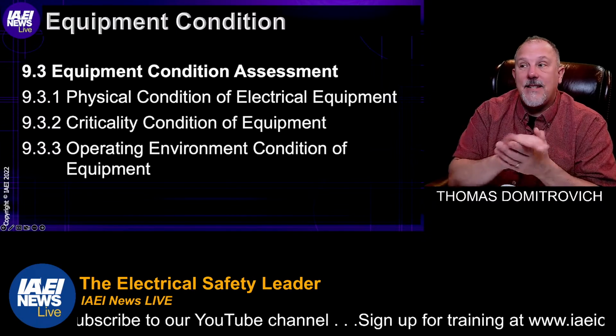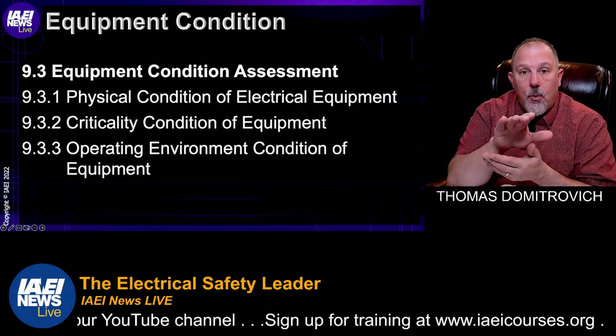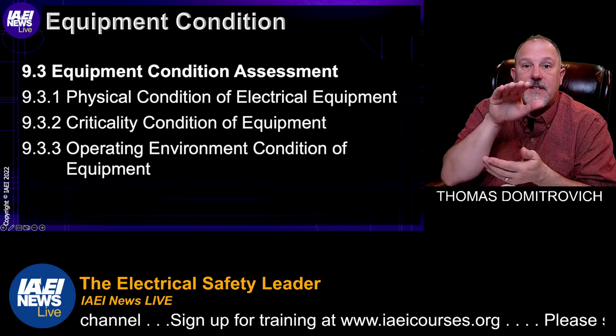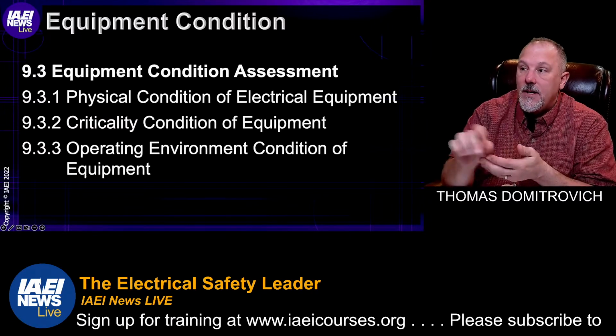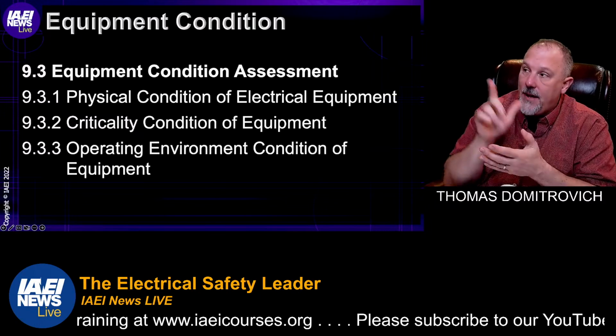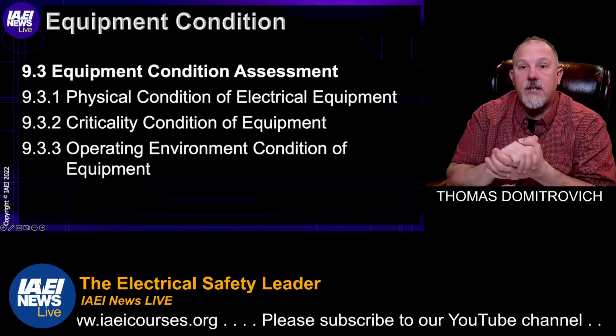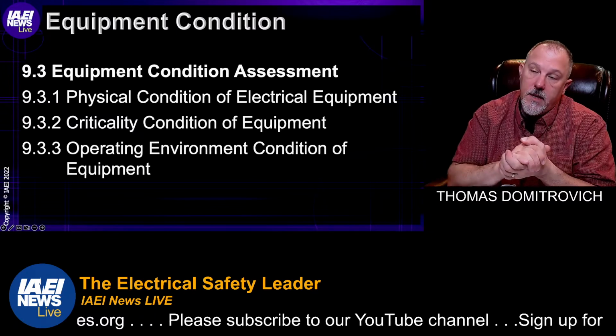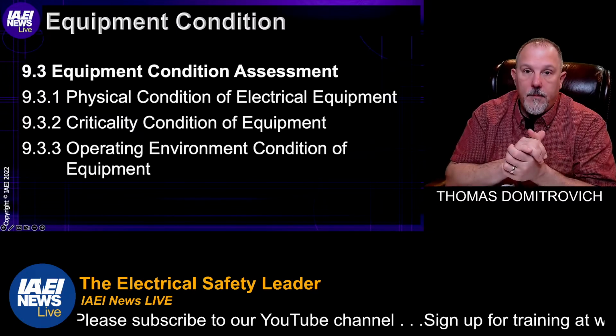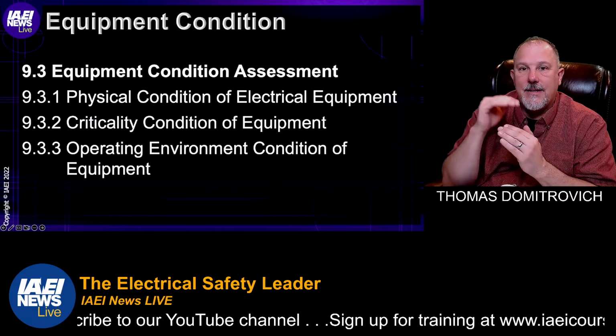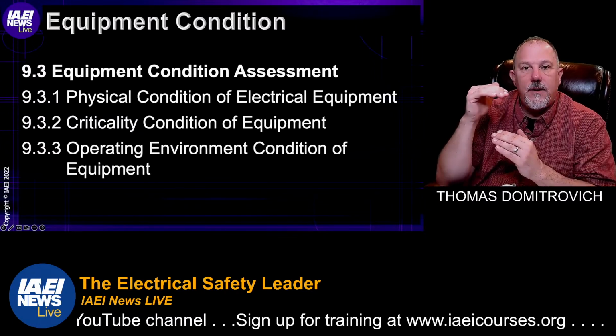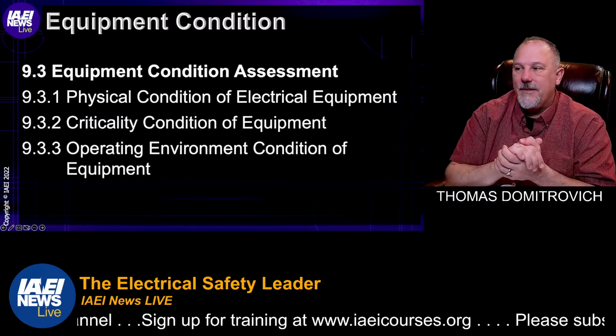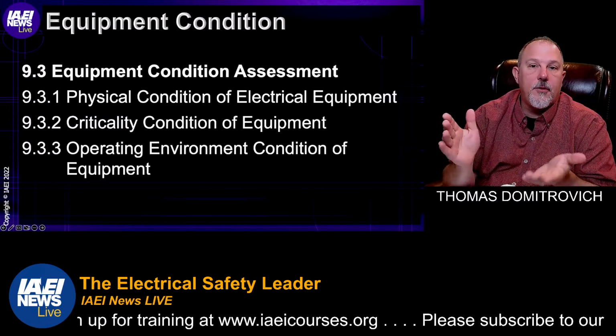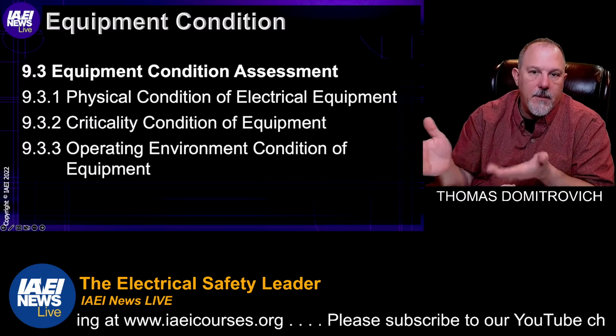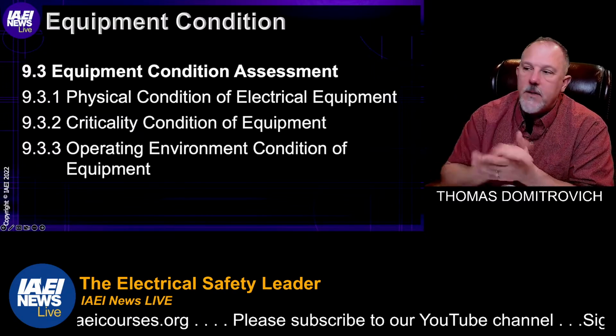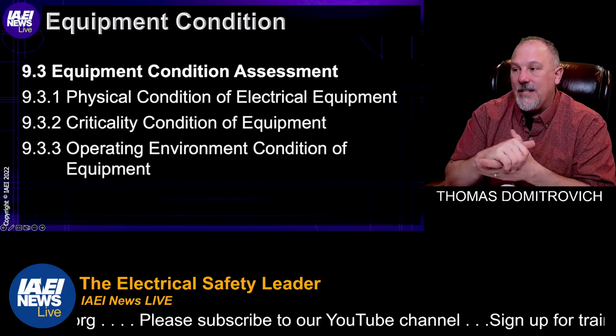But suffice it to say, this is input, a minimum requirement for your maintenance plan. Your facility may say, look, it's not going to kill anybody if that panel board fails, but it is going to cost our facility billions of dollars. You may elect to establish that condition higher. You may want to put a number 3 on it, even if it doesn't put lives at risk, is my point. This is a bare minimum requirement, right? And then you have the operating environment conditions.